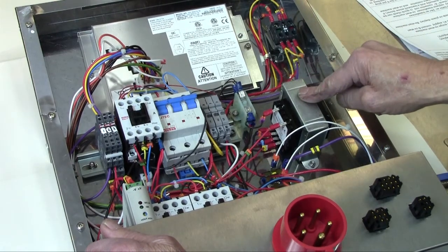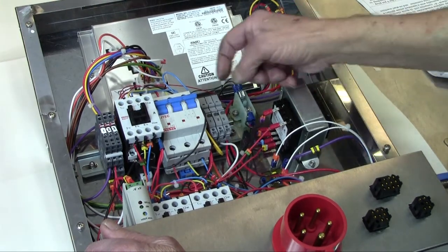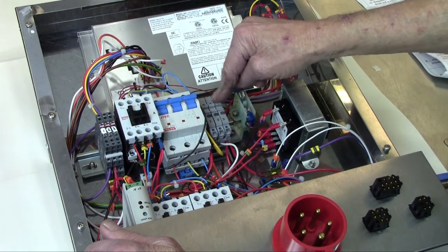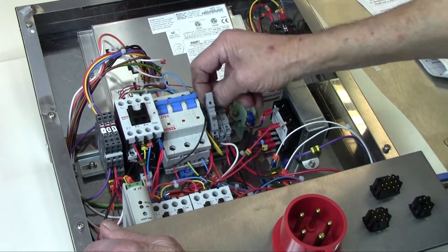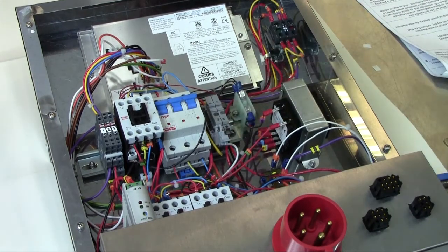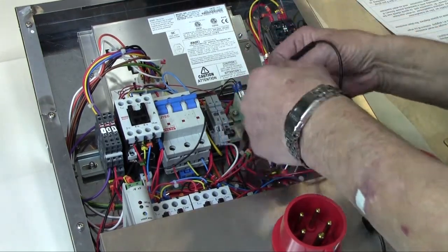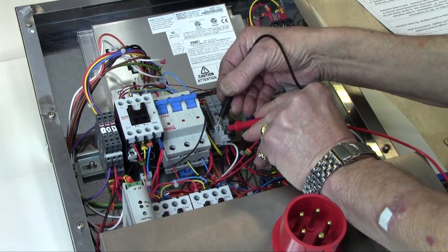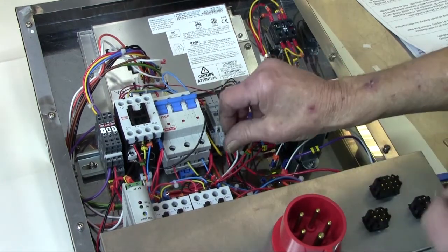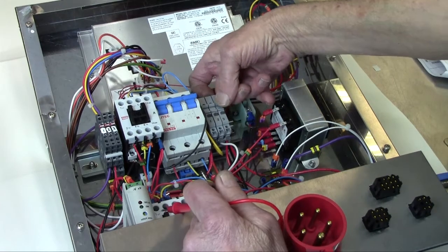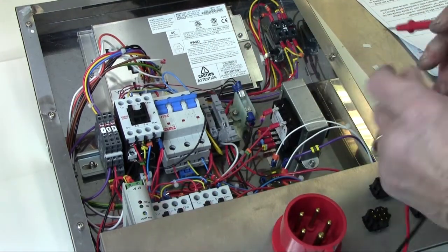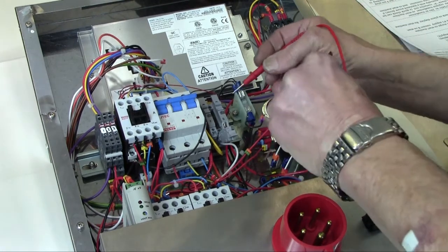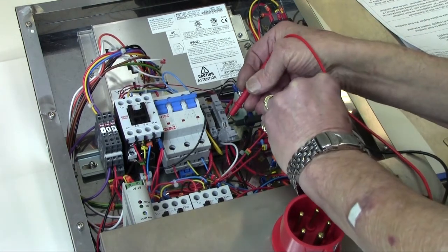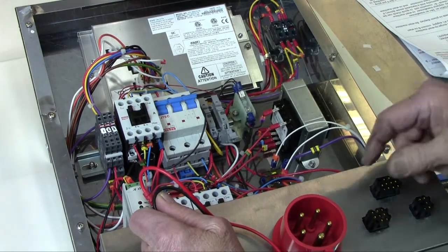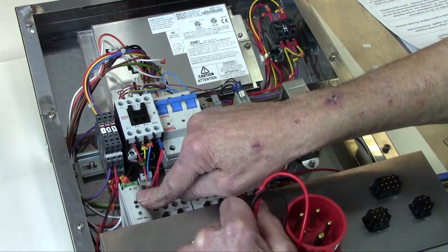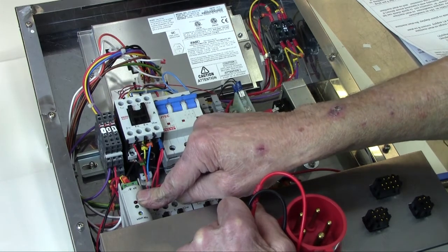If the high limit stat didn't need resetting, then check the 3 fuses. Number 1 fuse is a 220 to 240 volt 10 amp fuse. Check and replace if necessary. That's okay. Number 2 is a 24 volt AC 1.25 amp, which is from the anti-surge here. It's the output of the anti-surge.